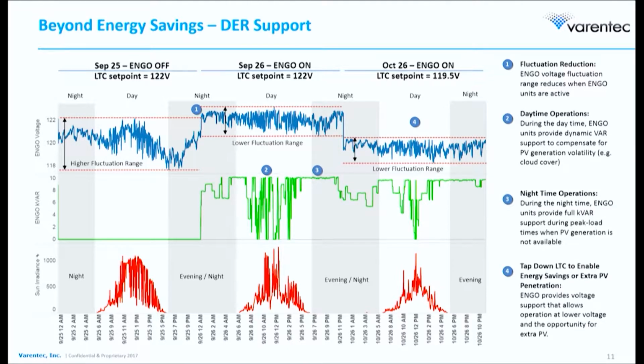As the solar picks up, you can see the top line, the voltage, also going up, even though typically load would push it the other way. That's because PV production is offsetting the loading. This is where they're having a problem, getting very close to the limit during the day, which is why they can't bring in more PV solar right now — they're hitting the ceiling.